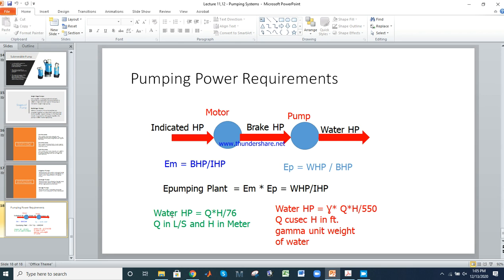Water horsepower (WHP) = Q × H / 76, where Q is in liters per second and H is in meters. Alternatively, WHP = γ × Q × H / 550, where Q is in cubic feet per second, H is in feet, and γ (unit weight of water) = 62.4 pounds per cubic foot. That is all for today's lecture. Thank you.